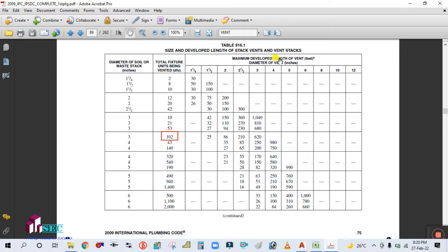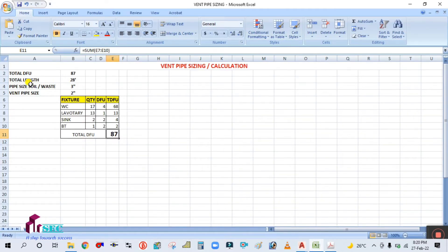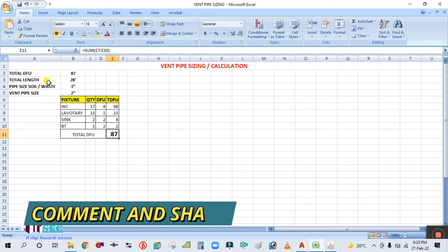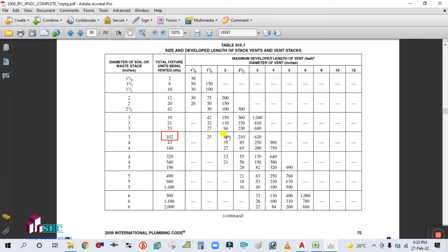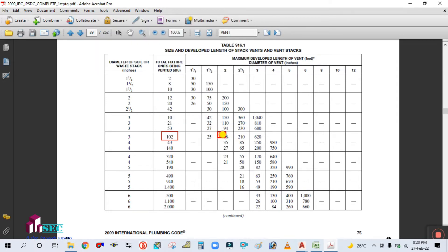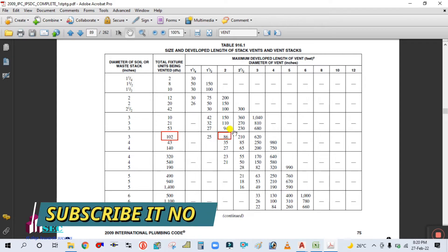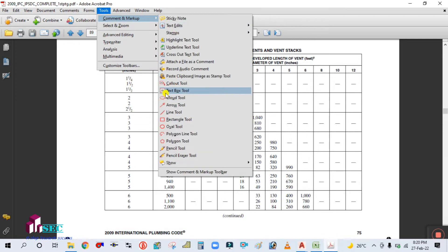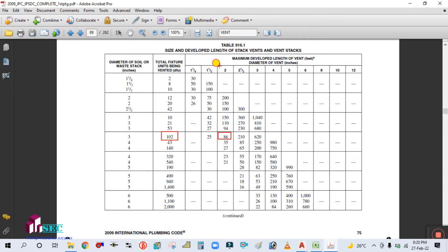You can see this is the maximum developed length in feet. In our project the total length of the building is 28 feet. Since 28 feet is less than the 86 feet shown in the table, you take the maximum value of 86 feet. Going above 86, you find the pipe size of the vent — which is 2 inch.